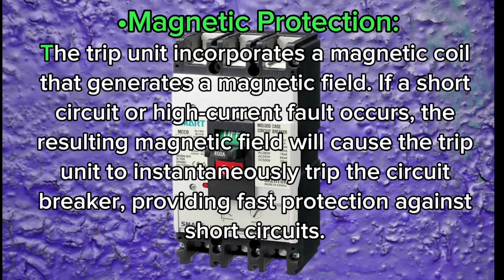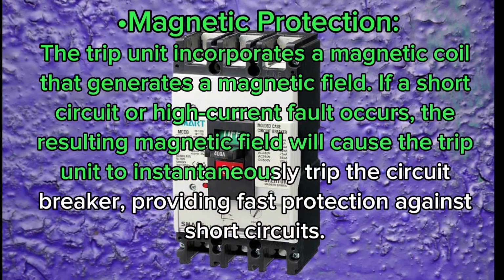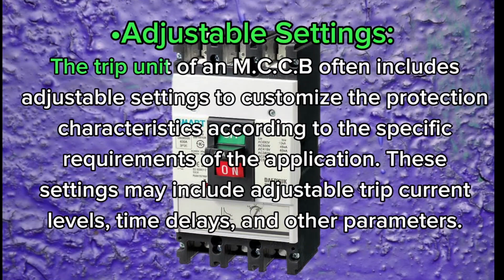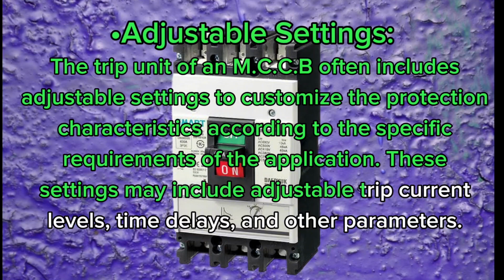Magnetic protection. The trip unit incorporates a magnetic coil that generates a magnetic field. If a short circuit or high current fault occurs, the resulting magnetic field will cause the trip unit to instantaneously trip the circuit breaker, providing fast protection against short circuits. Adjustable settings. The trip unit of an MCCB often includes adjustable settings to customize the protection characteristics according to the specific requirements of the application. These settings may include adjustable trip current levels, time delays, and other parameters.